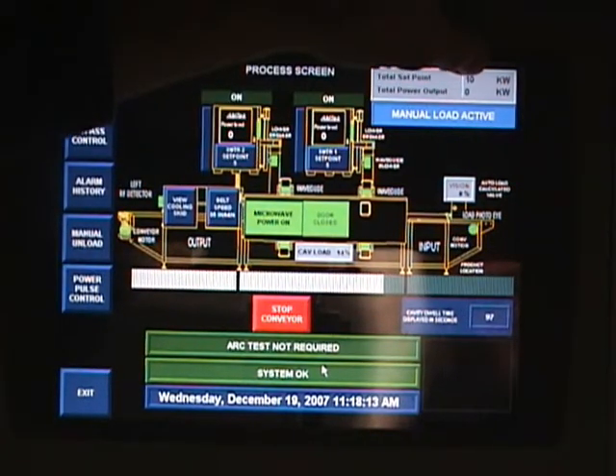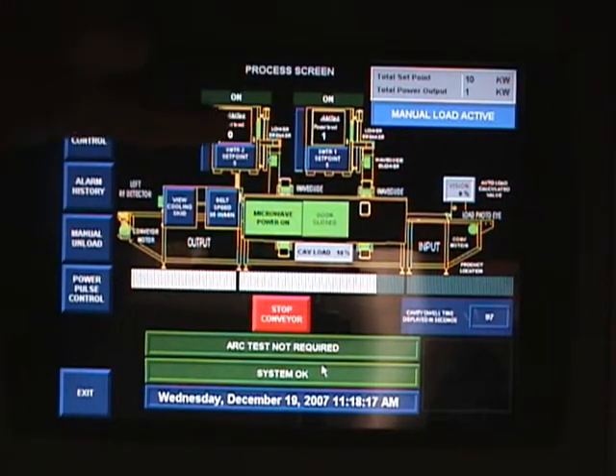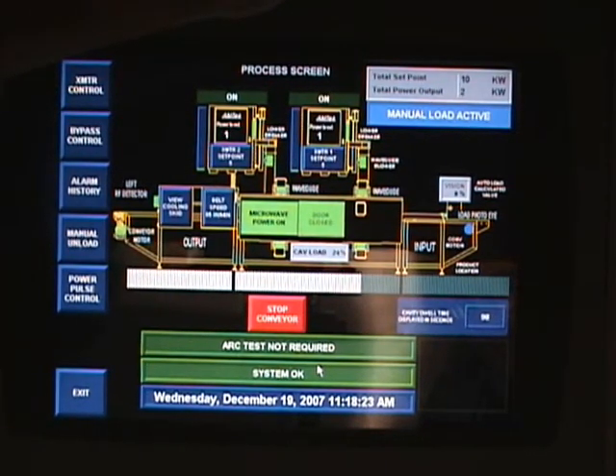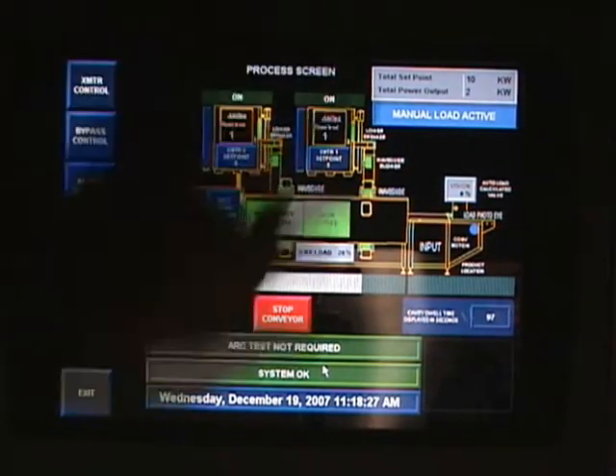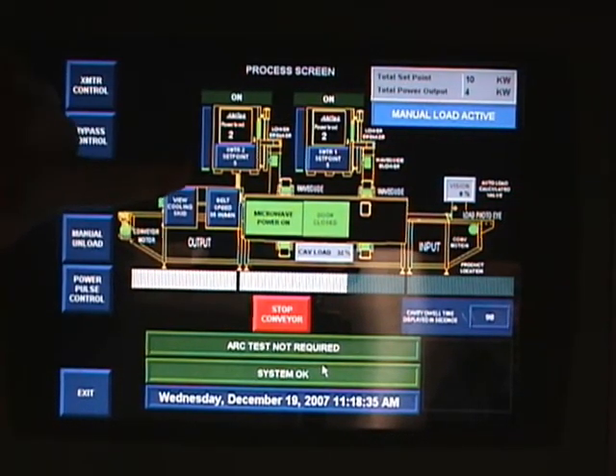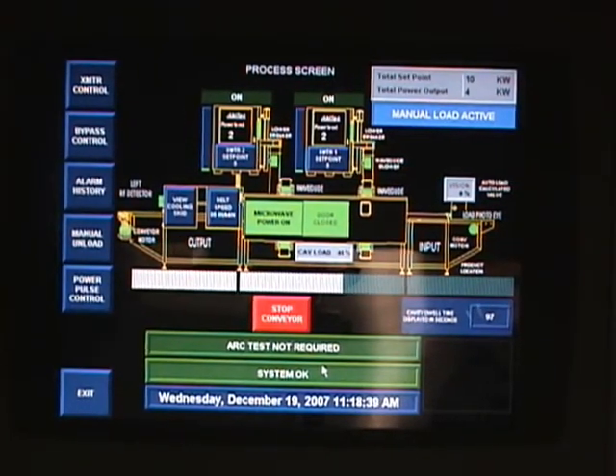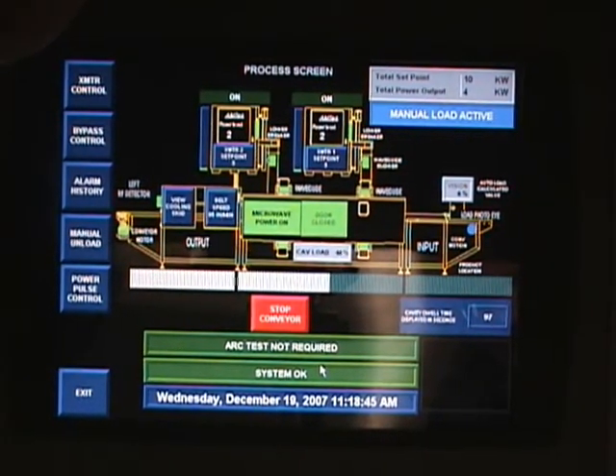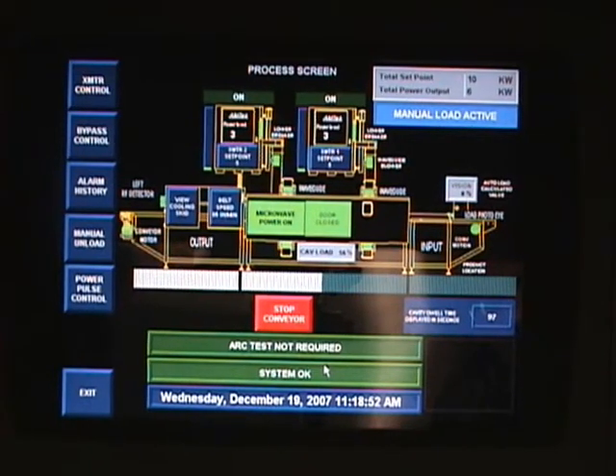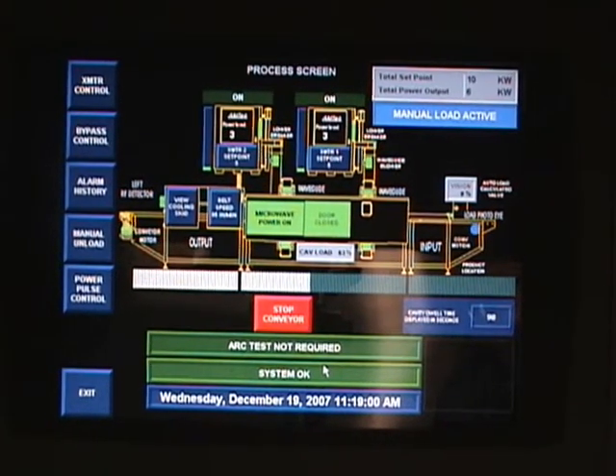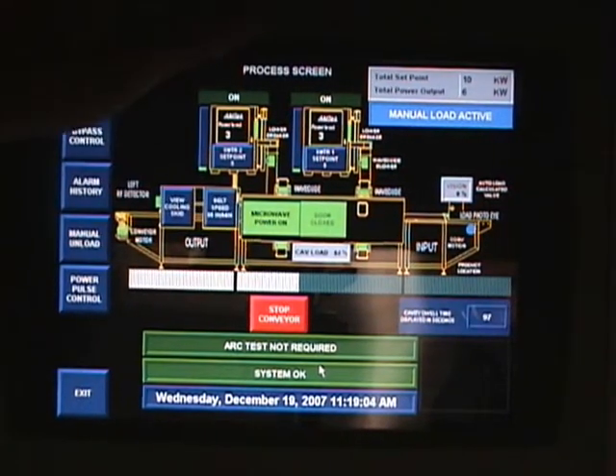This is the total set point of the oven — there are five on each transmitter. You can see this transmitter's coming up. There's a bar chart here that shows the percentage of one hundred that the transmitter's operating at at the current level, so all the way to the top would be 100. Down here it shows the dwell time that the actual product's in the oven in seconds. Right now it's at six kilowatts, about three quarters full.